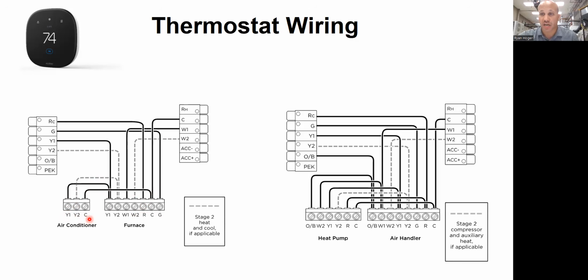Maybe you're lucky and it's the one job where somebody pulled 10 conductor wire because that's what they had on their truck that day, but they probably pulled exactly 5 wires. So on a heat pump, you still have R and C for power. You still have G for fan. You still have Y, but instead of Y being cooling, Y is now compressor. You still have W for your auxiliary heating situation. And then you have an extra wire from the thermostat over to the air handler or furnace. That is labeled as O/B, typically because it's either orange or black. And the orange and black meant different things back in the day.